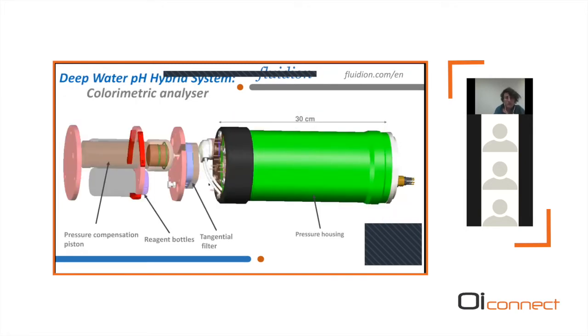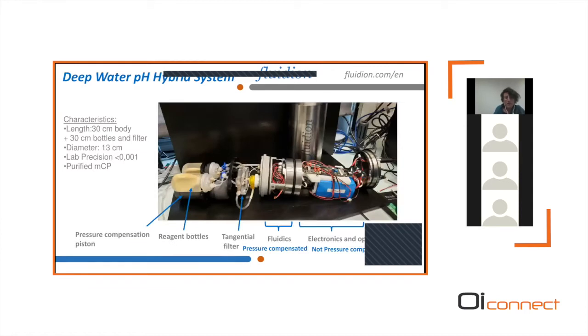But now we moved on to an in-situ version of the colorimetric analyzer. And here on this drawing, you can see this is a pressure-proofed housing for the electronics. And here on the left, these are the components that need to be accessible so that they can be replaced for maintenance, such as the reagent bottle here and the tangential filter. So if we look in more detail, this is a picture of the analyzer outside of its housing.